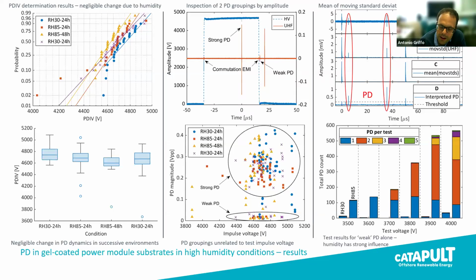We have conducted a very large number of experiments in different environmental conditions, combining various levels of temperature and humidity over the long term, over several weeks of testing. The first aspect is that the discharge event is at very high frequency, into the hundreds of megahertz and into the gigahertz range. So the signal processing to capture and measure partial discharge is quite challenging, especially in the presence of high commutation noise from the switching. That's where we introduced the methodology shown in the top right, based on the processing of the moving standard deviation of a signal captured by a high frequency antenna.